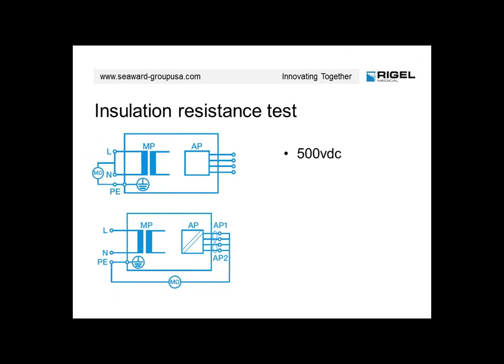So the insulation resistance test is done at 500 volts DC. This voltage is, of course, generated within the test device itself. And we do the mains input, and we will also do the applied parts at the 500 volts. And what you see is that the like applied parts are tied together, so it is a single test for like applied parts.